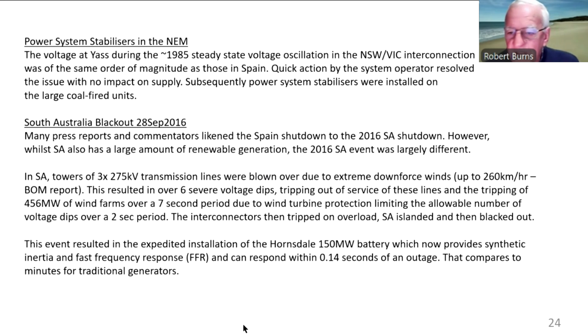The South Australian event was largely different. It was caused by 3 275 kV transmission lines being blown down by extreme downforce winds. It's a bit like a tornado. So it blew down 3 transmission lines. There were 6 severe voltage dips as the lines hit the ground and things reclosed and then tripped back out again. And it actually tripped 456 megawatts of wind farms in their case over a 7-second period due to a limit on the number of voltage dips that you can have over a 2-second period. I'd never heard of that one before, but that's what the wind farms have got as well as normal things. The interconnectors then tripped on overload, South Australia islanded and blacked out.